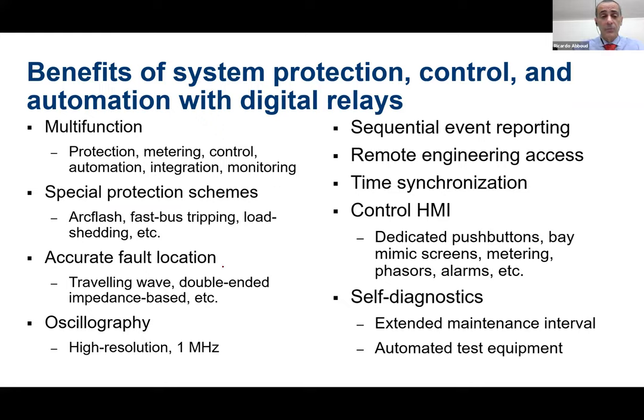Accurate fault location, this is really important. With the digital relays, we can have a traveling wave fault location. So in the same device, you have protection, metering, control, and also the traveling wave fault location. For transmission systems, this is really important to pinpoint the fault when you have a sustained fault. You can also have double-ended impedance-based fault location. If you have communication between the two relays at the two ends of the transmission line, we can implement this double-ended impedance method, which is very accurate also.